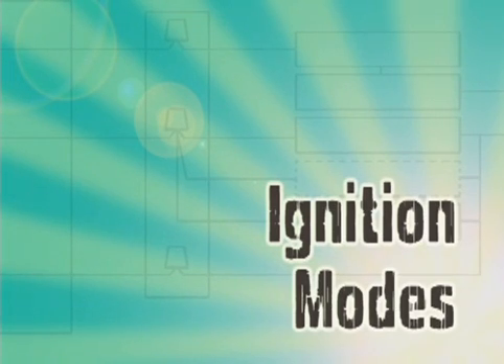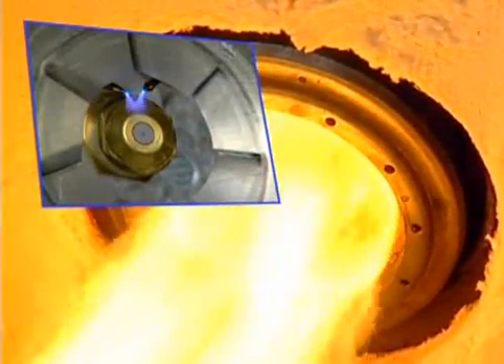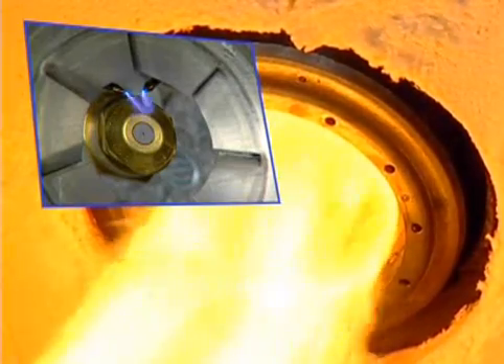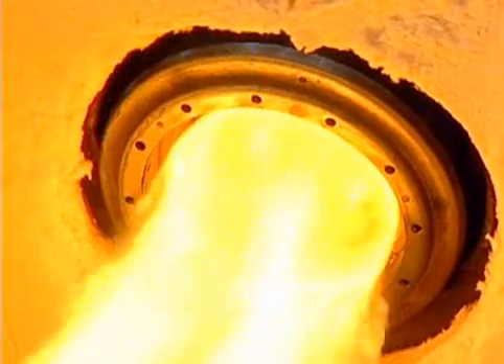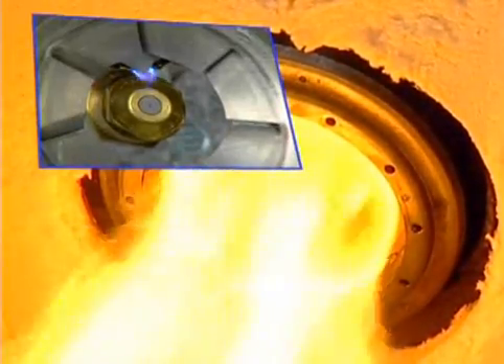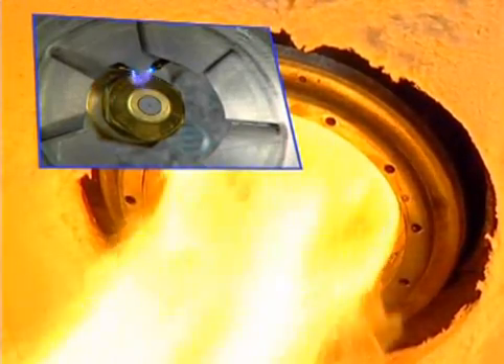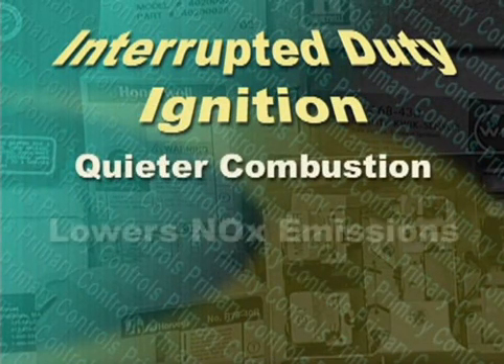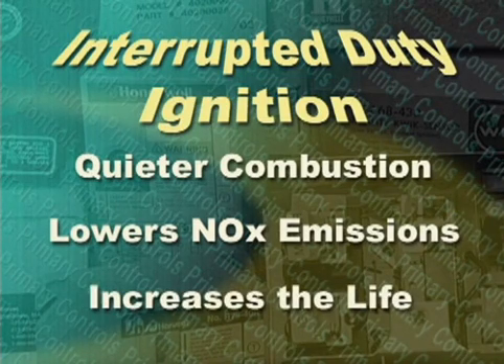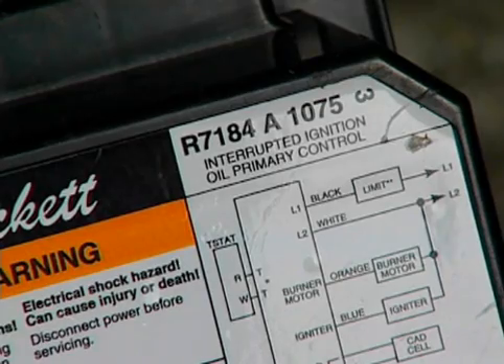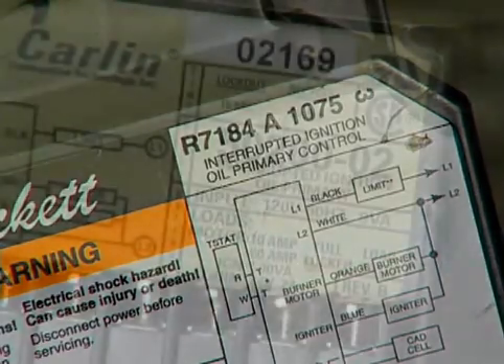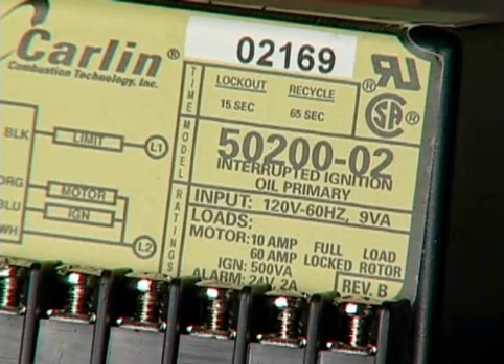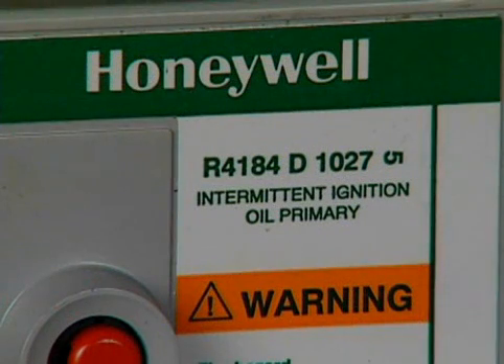Oil heat systems operate in one of two ignition modes: intermittent duty or interrupted duty. Intermittent duty ignition means that the spark across the electrodes that ignites the oil is present throughout the entire time the burner is running. Interrupted duty ignition means the spark comes on for a short time at the beginning of each burner operating cycle and is turned off once flame is established. Interrupted duty ignition is much better because it makes for quieter combustion, lowers NOx emissions, and increases the life of the ignition system. Primary controls can be designated either interrupted duty or intermittent duty. Primary controls that allow for interrupted duty ignition can be adapted for intermittent duty ignition, but primary controls designed for intermittent ignition cannot be used for interrupted ignition.